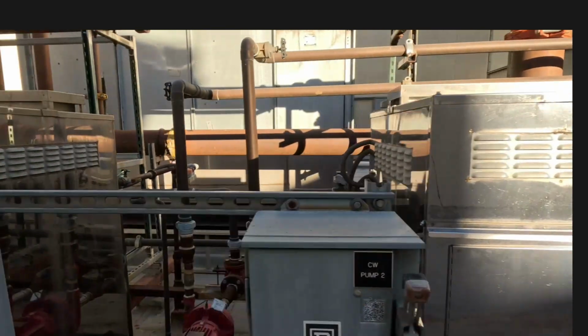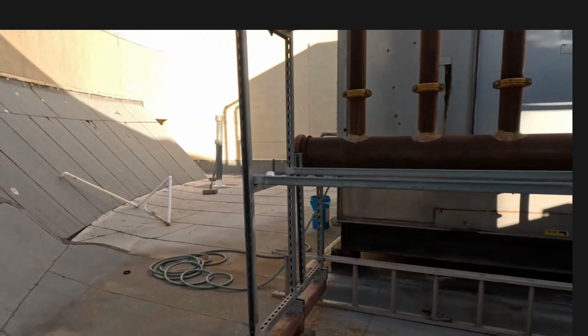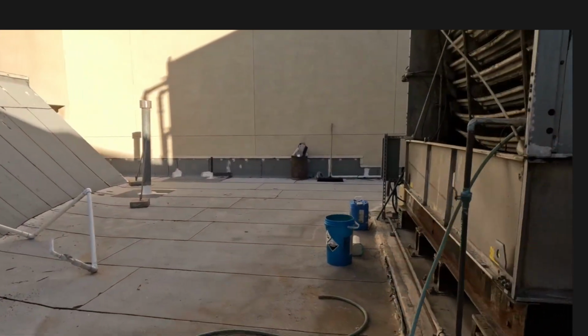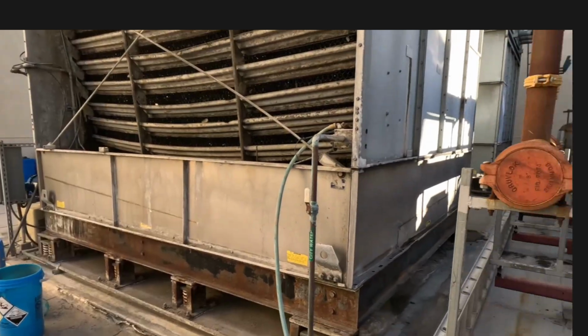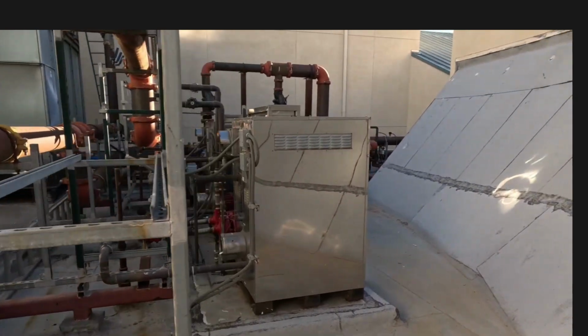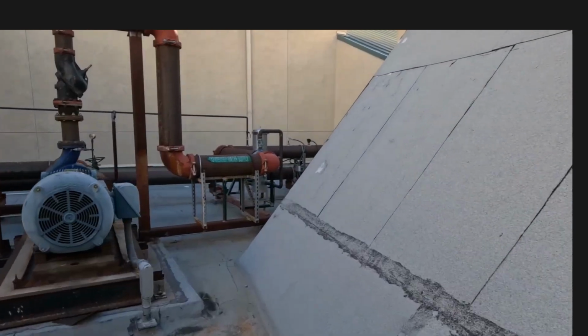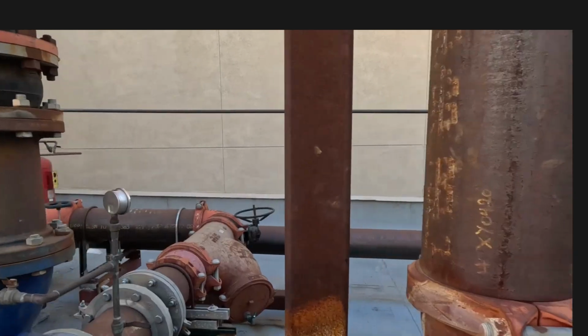You suspect those pumps are too big for this system, and that's why they're causing this noise, because on the suction side they are operating in a negative pressure. Let me show you real quick those pressure gauges that I have on there, and I'll show you it running in a negative.